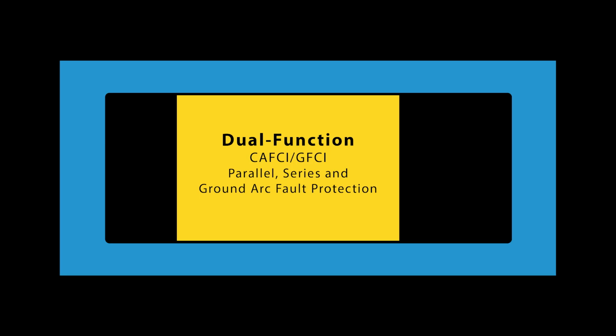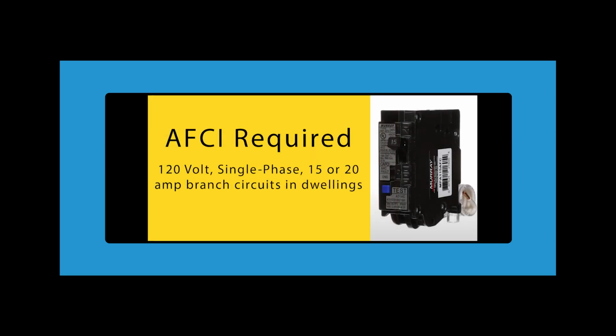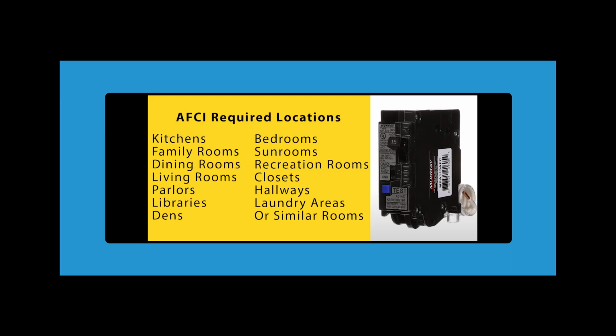Now, while all that sounds great from a safety perspective, this extra protection can kick in unnecessarily. You're probably wondering if AFCI breakers are required for your home. The short answer is yes. The National Electrical Code has guidelines mandating AFCI protection for specific circuits in residential buildings. As of 2020, AFCI protection is necessary for most 120 volt single phase 15 or 20 amp branch circuits supplying outlets for devices in many areas such as kitchens, family rooms, dining rooms, and so on.